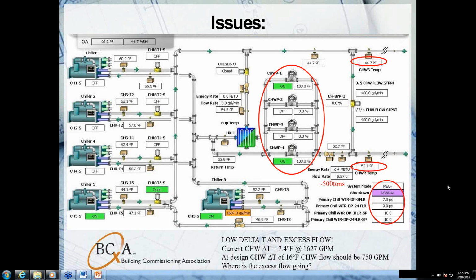It's not that we're abandoning the complete approach, but we're saying that if you're in this spring, fall seasonal weather, just valve it off, disconnect it, and then once you get into the summer, if you want to run series counterflow, you can do that for the efficiency. But for a lot of the year, they're just going to run one of the machines.